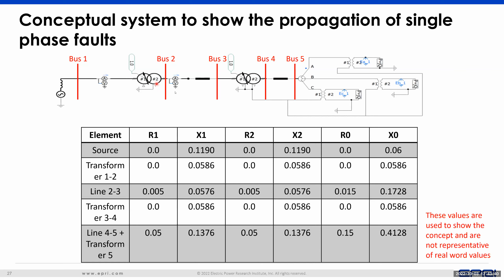So if we just understand the concept behind how this transformer winding impacts the way in which faults will be propagated, we have here a delta star winding and a star star winding, and we would apply the fault here on bus 1, and we want to see how it propagates down to the DER here. A lot of you might have derived these kinds of sequence network diagrams in power systems classes, wherein you can understand that if you have a star-star connected transformer versus a delta-star connected transformer, you essentially have a change in the structure of the zero sequence network, and it also results in changes in the angle in the positive and the negative sequence network.